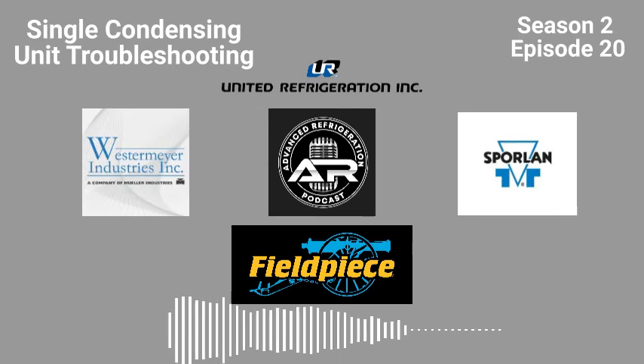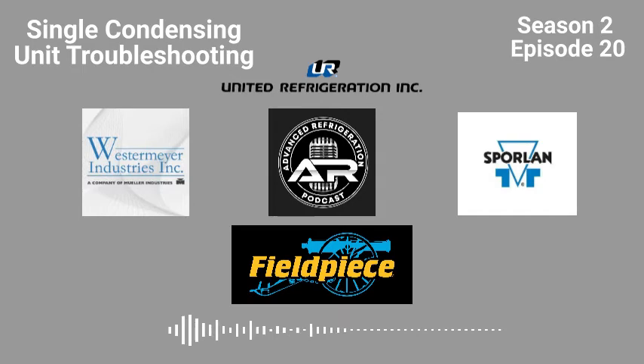But when using pulse valves, I would like to see EPRs being used. Unfortunately, in this instance, on the single condensing unit, we can't, because our suction pressure is already running low. It's running so low that it's actually causing the compressor to shut down on overload, because it's running outside of its operating envelope for way too long. That's where these X lines would come in, like with these digital compressors, but I honestly don't think they could take it. No, you think they'd be unloaded too much? I don't think they would last. Really? I think they would get beat up way too much, with the unloading and loading and all that stuff.